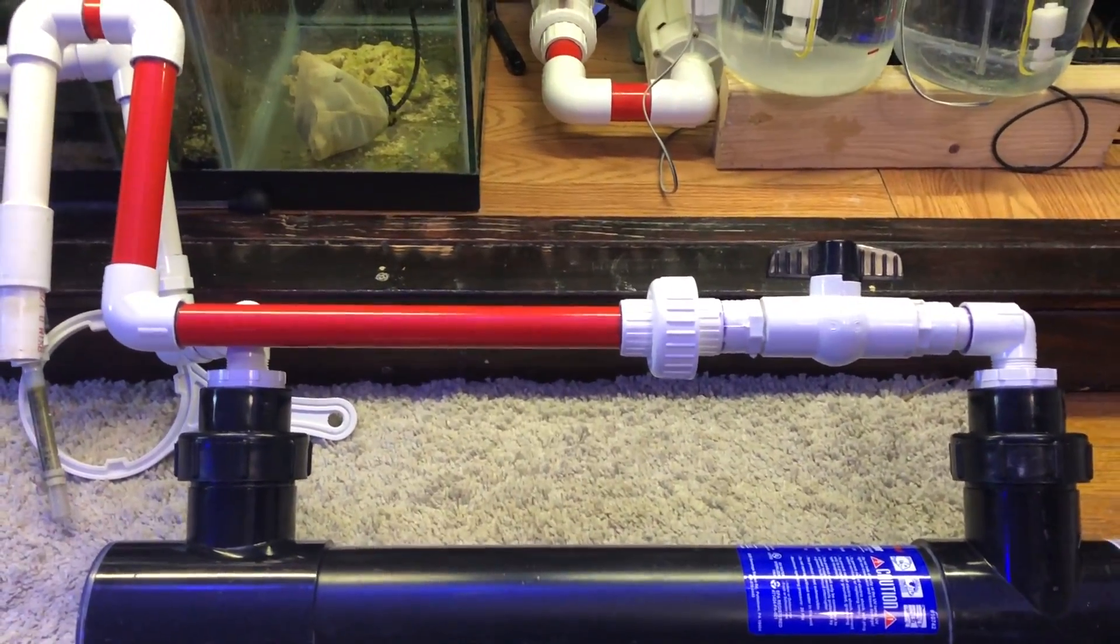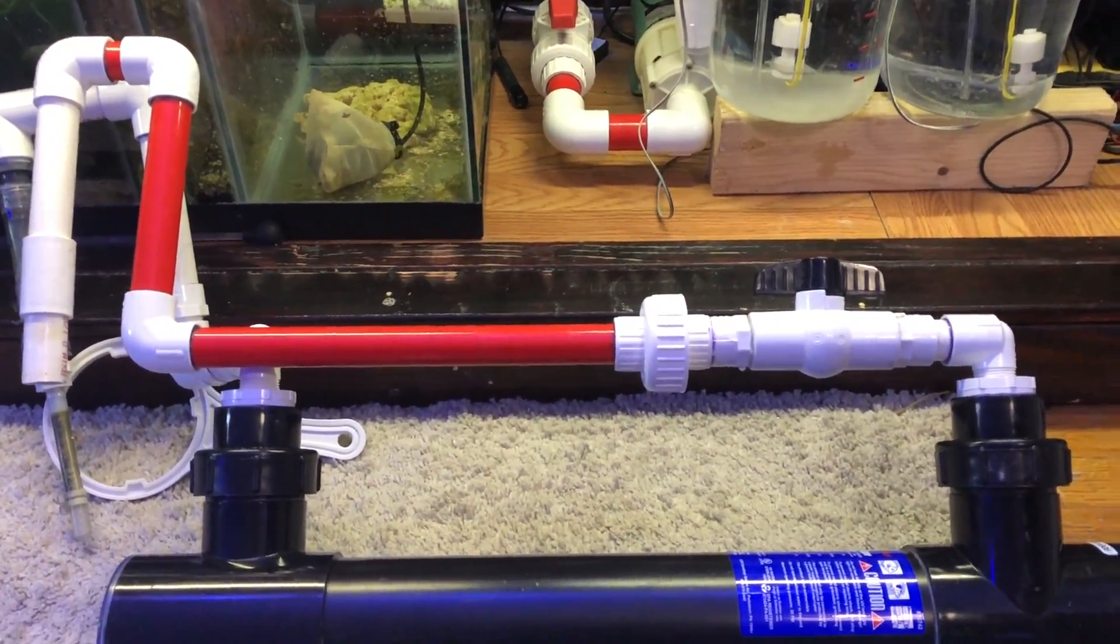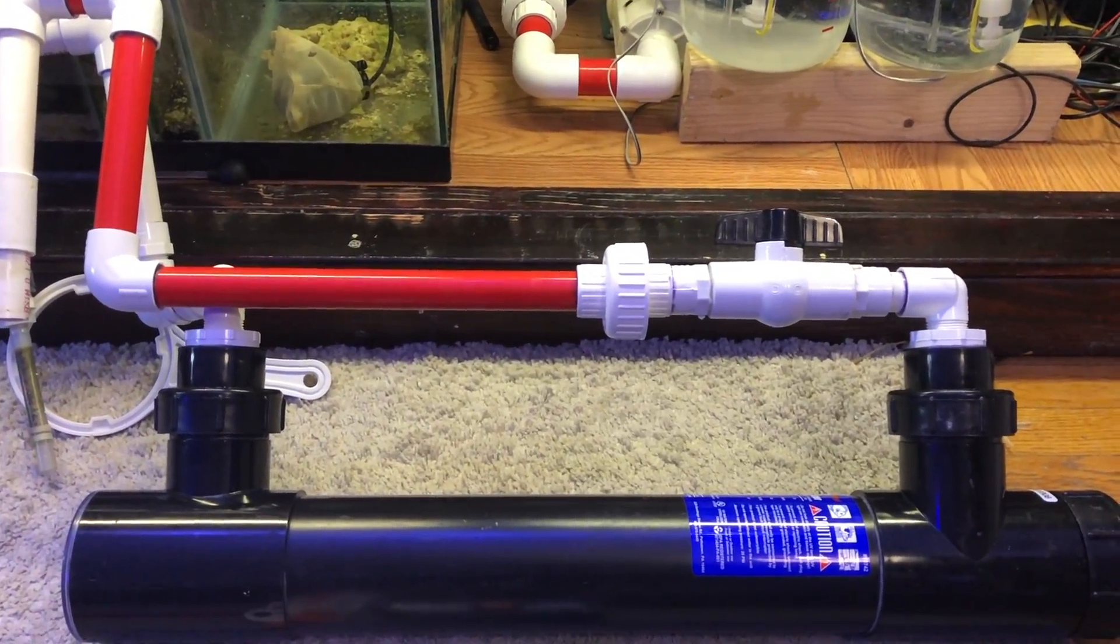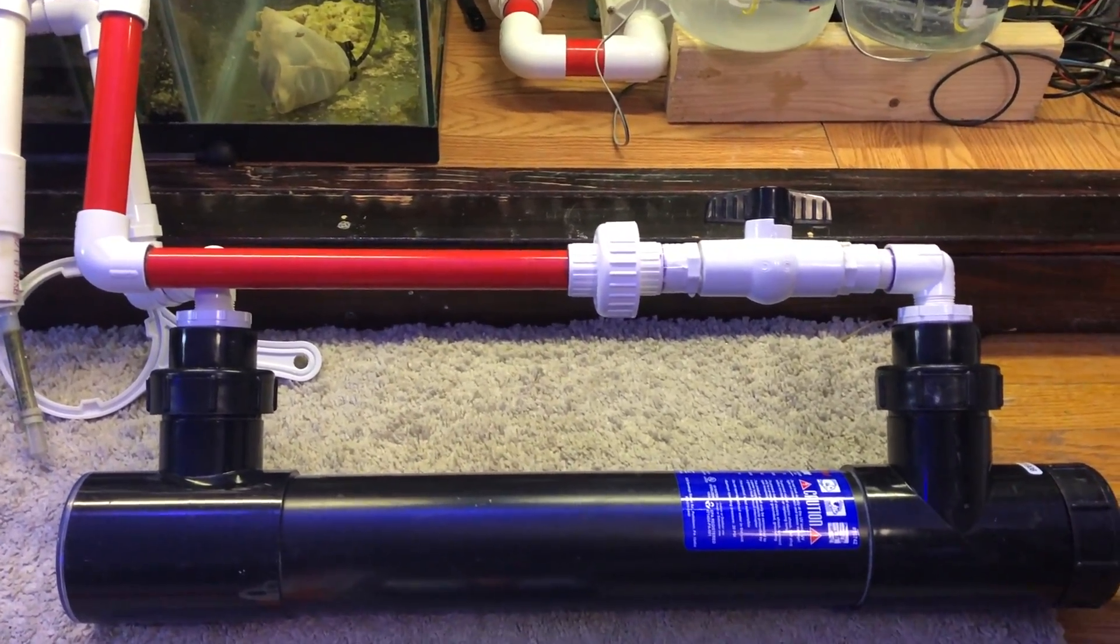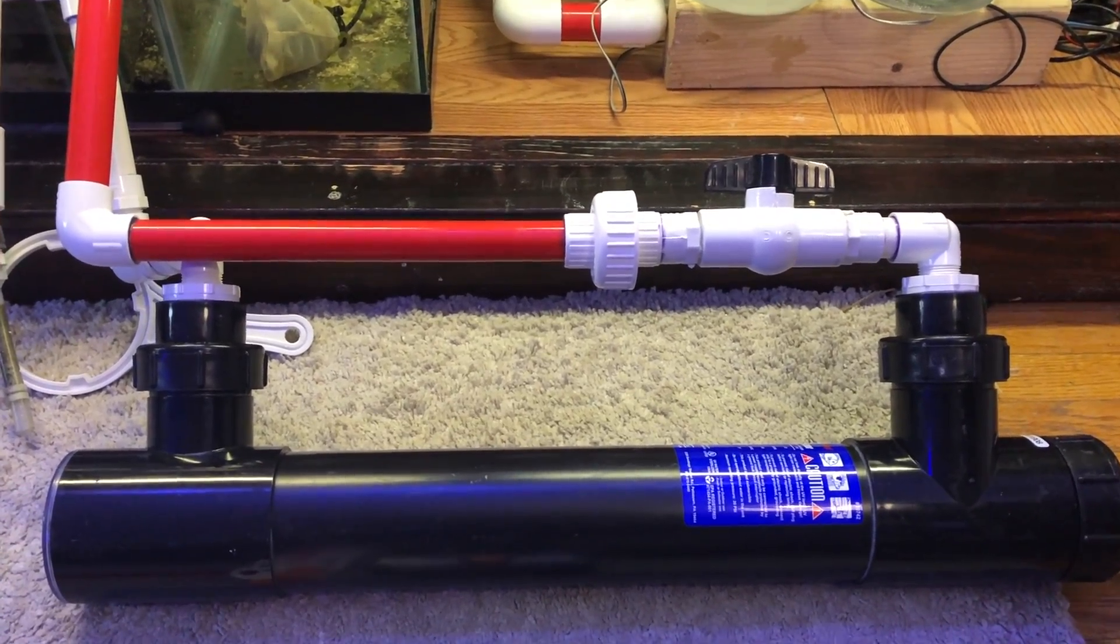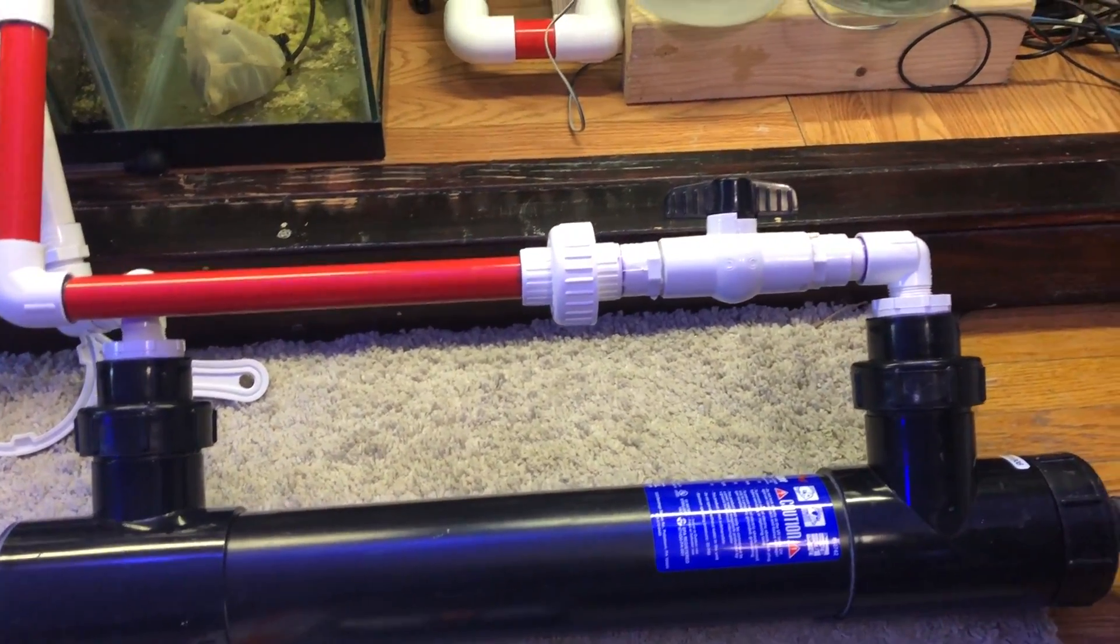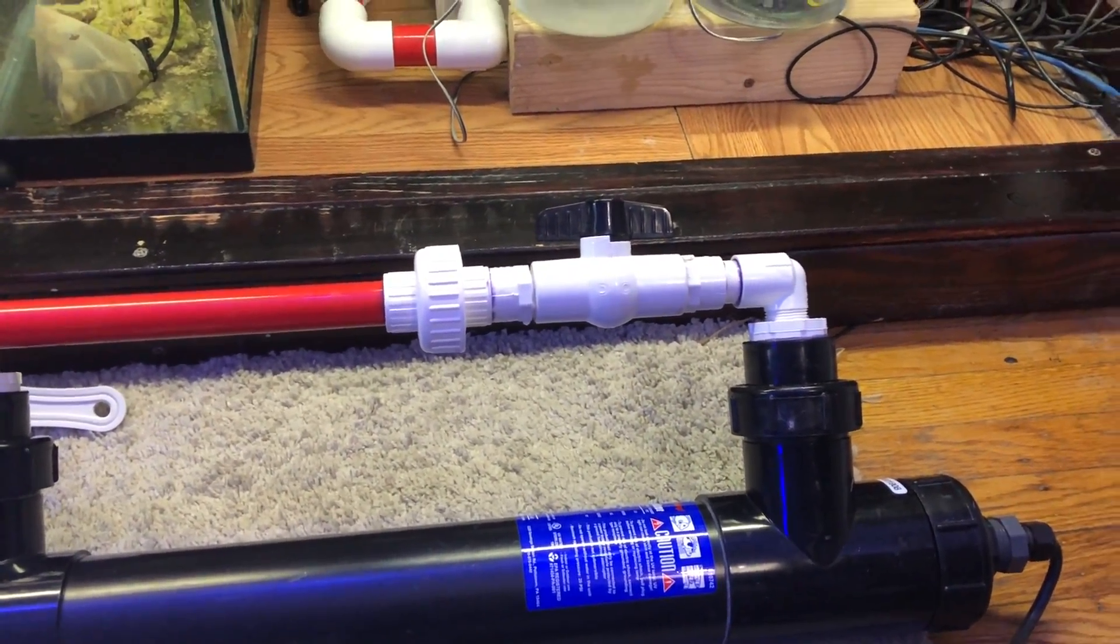I want to monitor the flow coming through here and make sure I'm keeping it at the proper flow rate, which for this model UV sterilizer is between 79 and 131 gallons per hour.